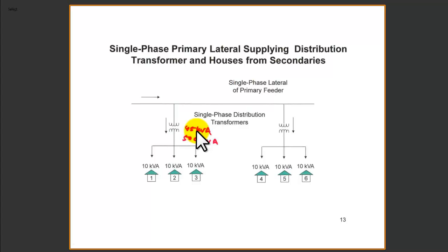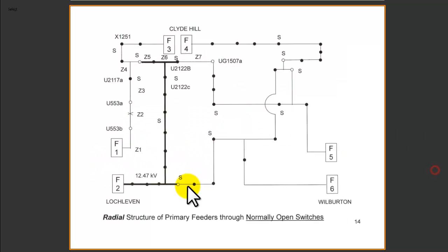And sometimes we don't really connect this distribution transformer when we build more houses in the area. We could do that, but careful planning has to be done so that this distribution transformer doesn't get overloaded. So for example, if you're going to build another two residential houses here under this distribution transformer, which might hit 50 kVA, presuming that each of the two additional households will consume 10 kVA, then this transformer could either be replaced with a new one, or the utility probably has to buy an additional distribution transformer to connect to those two new households.